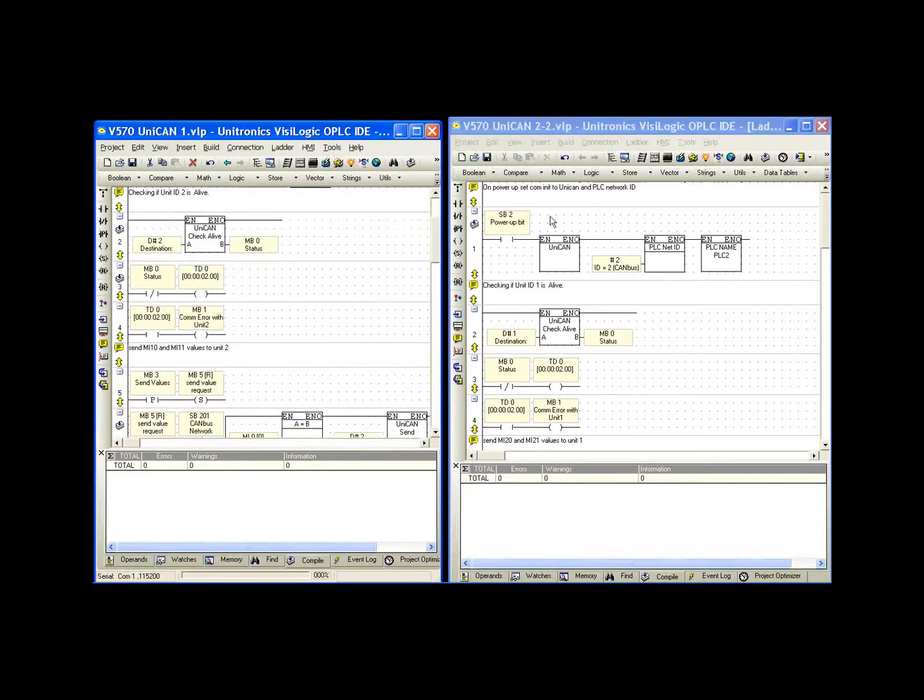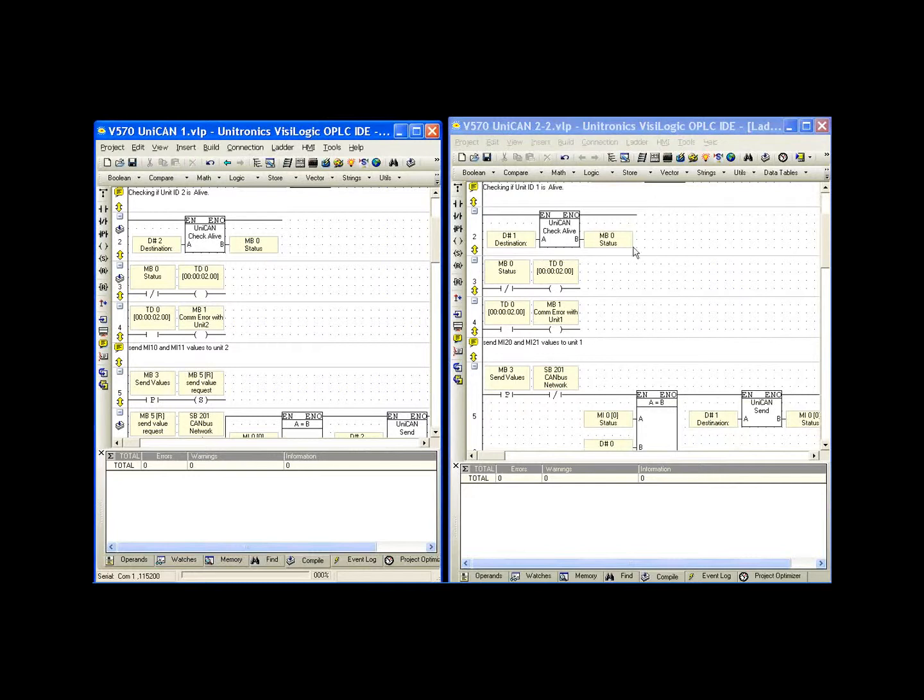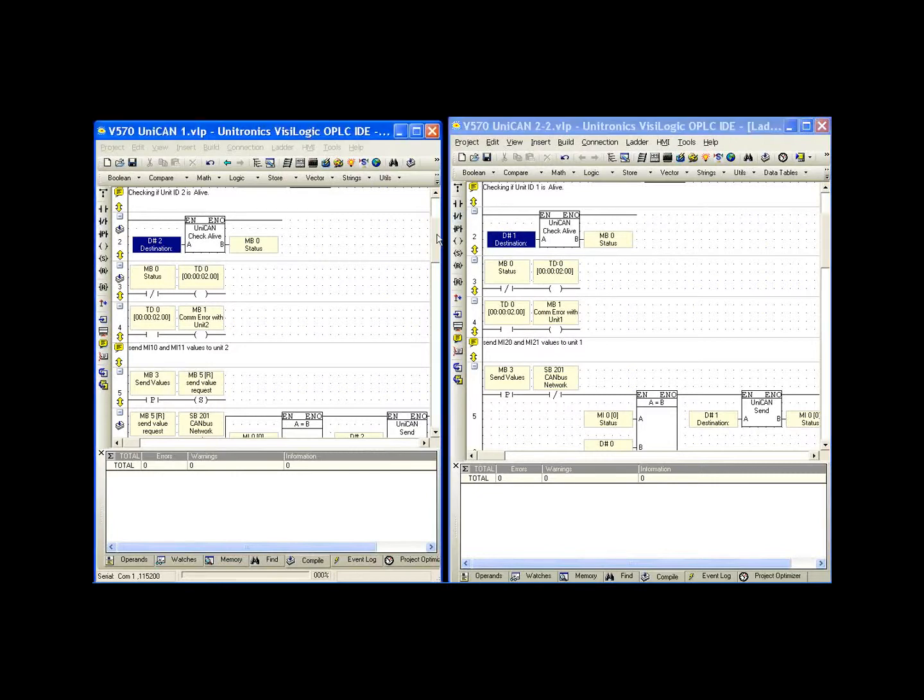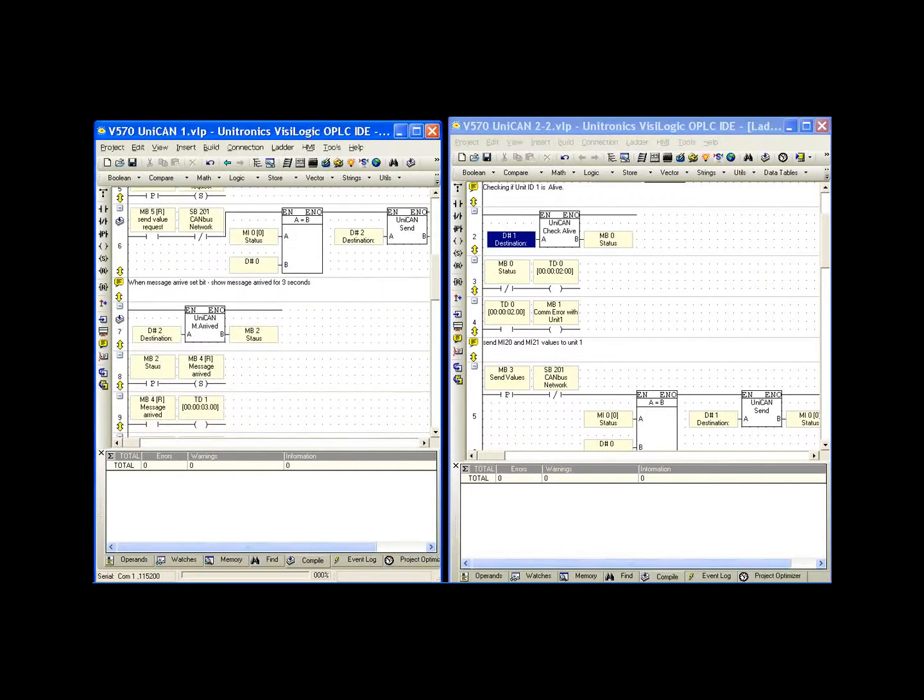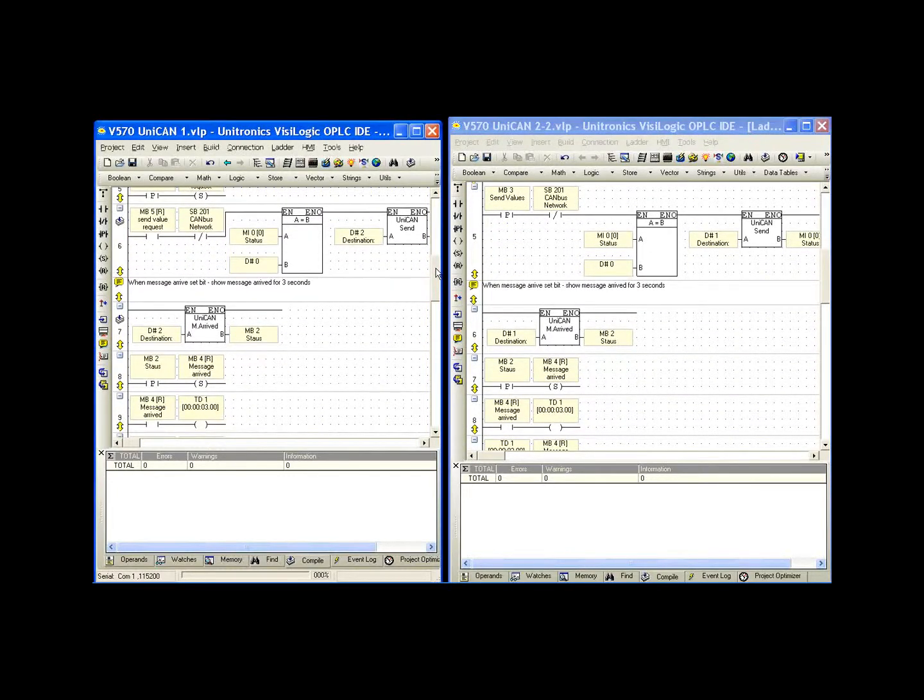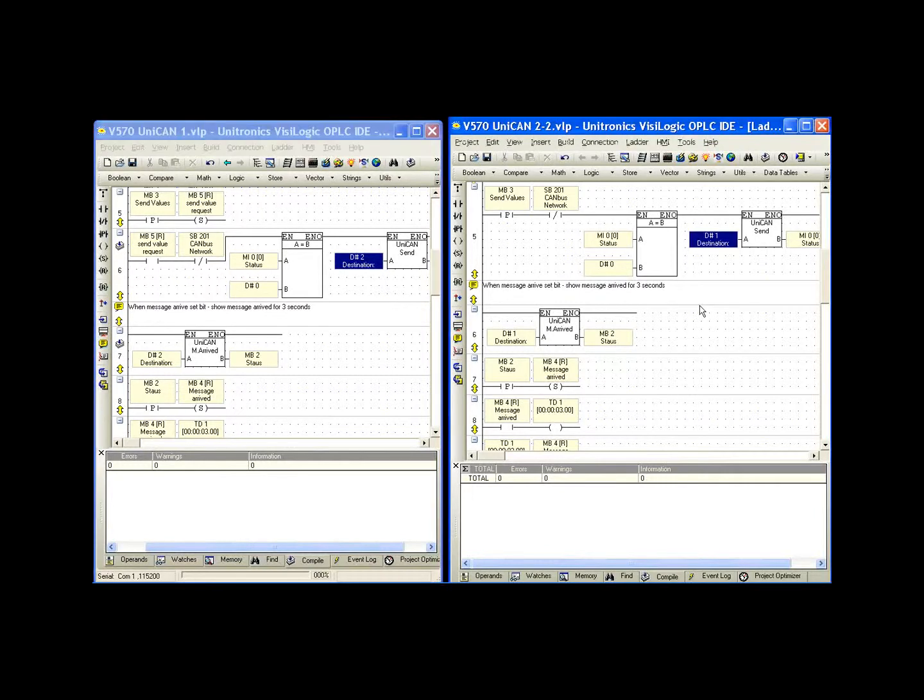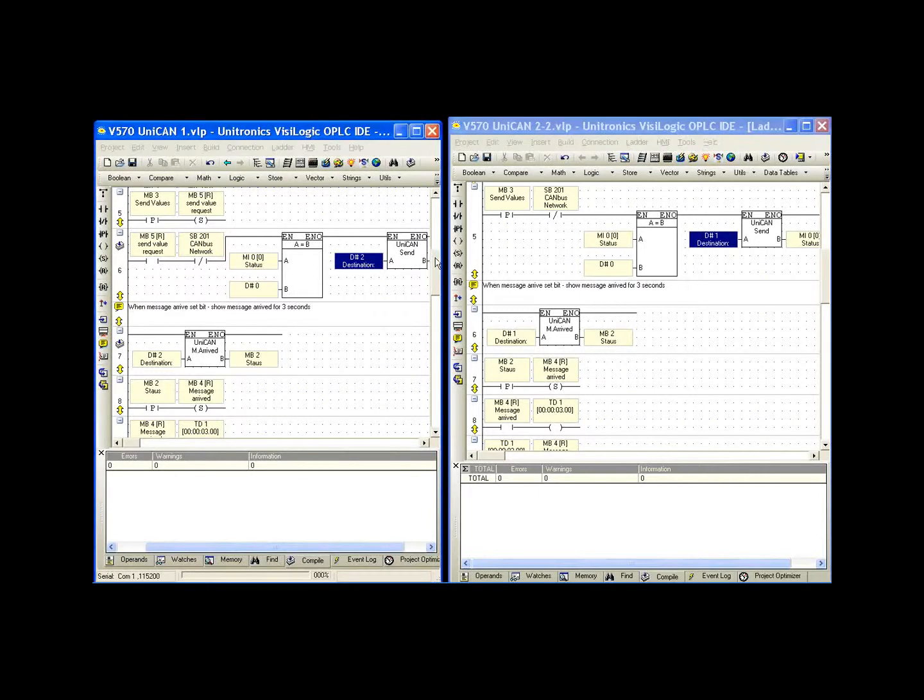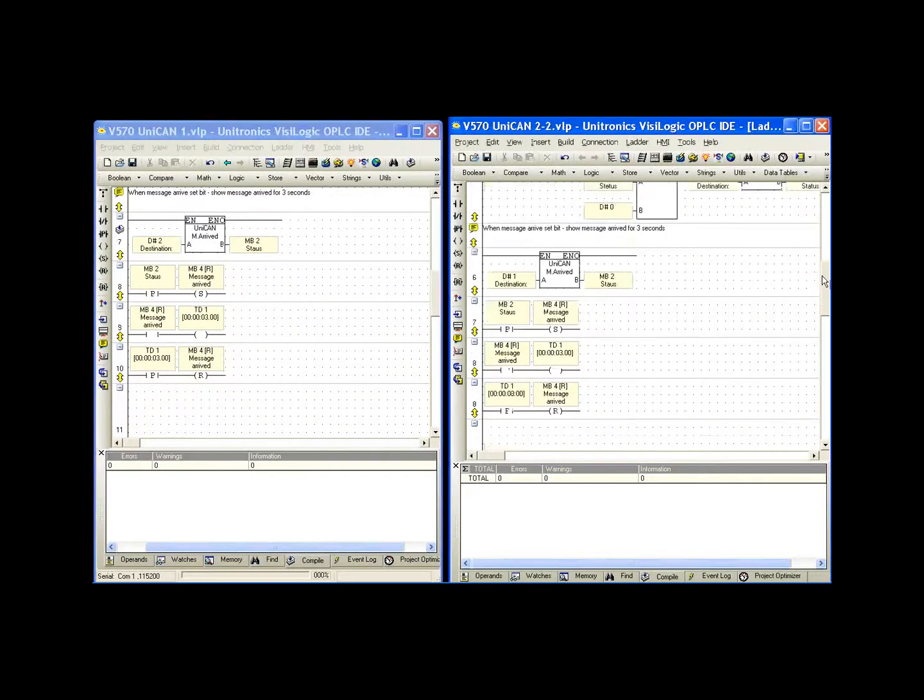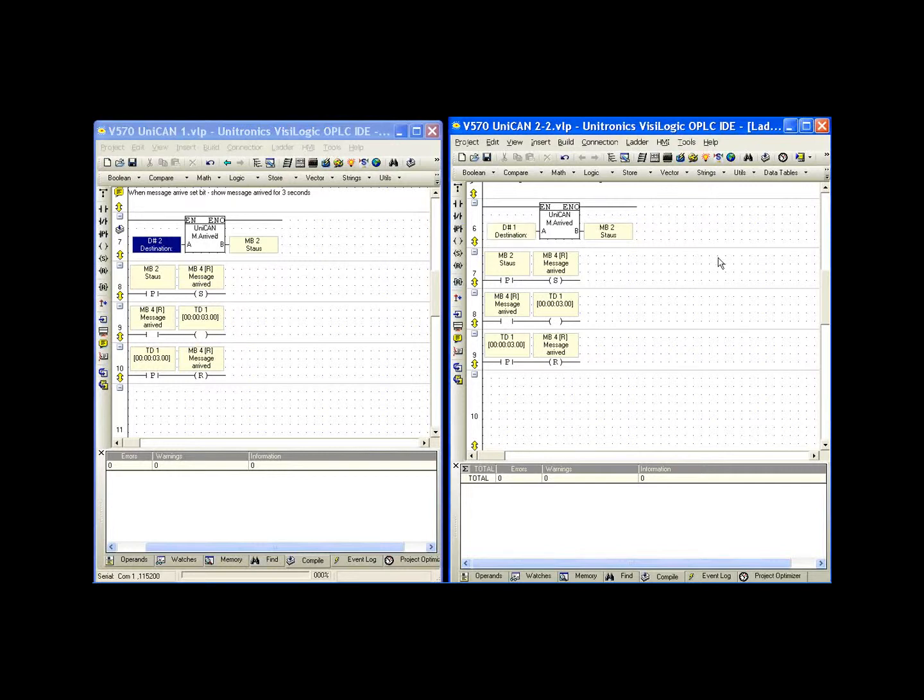That being said, everywhere we have a function with an ID number, we should match the opposite one. We had Unit ID 2 for the check alive. Now we have Unit ID 1 for the check alive. The timer network is the same. If we continue down to the send command, we'll see that these networks are set up the same as far as the send goes. But the Unit ID, Destination ID is different. And the information in the message arrived is also different. Very similar programs. The only difference is the network ID so we can communicate to the appropriate controller.